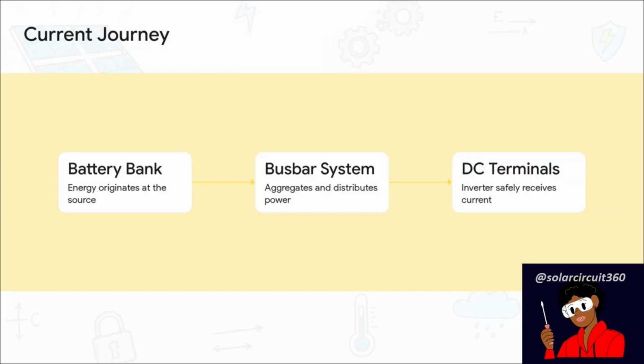Let's actually walk through the physical path the energy takes to see how this builds a controlled energy flow. Think of it like a spatial map. Step 1, the energy kicks off at the battery bank. Step 2, it travels into the busbar system, which acts like a grand central station, aggregating and distributing that power. And step 3, it finally hits the inverter DC terminals.